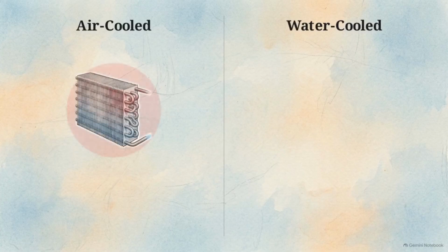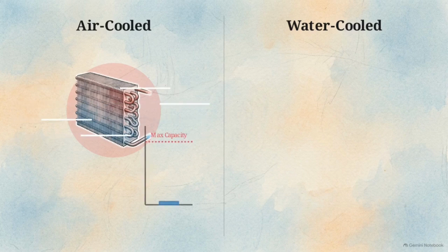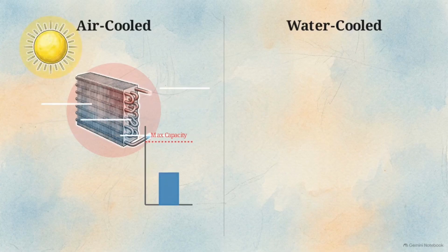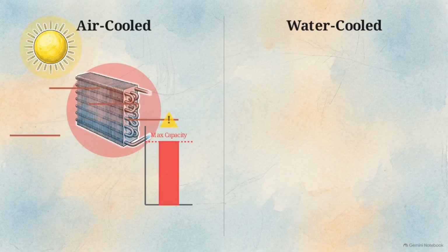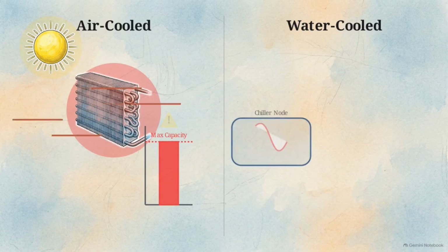The physical architecture of the entire chiller plant is ultimately dictated by the condenser, specifically where it sends the heat it just collected. In this side-by-side comparison, the left side demonstrates an air-cooled architecture. Fans push ambient outdoor air directly across the heated condenser pipes to carry the thermal energy away. This method is straightforward but limited. Because it relies entirely on ambient outdoor temperatures to absorb the heat, it lacks the thermal efficiency required for anything larger than a small or medium capacity load.